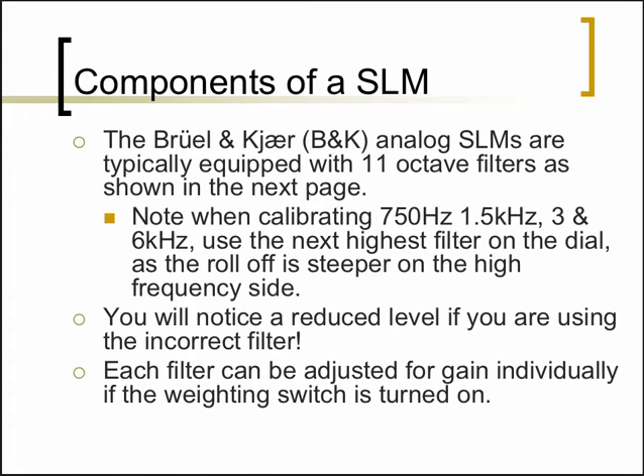So the B and K sound level meters, for instance, have 11 octave filters that are engaged depending upon the frequency that you're testing. Just a word of advice: if you're testing any inter-octave frequencies like 750 hertz, 1.5, 3, or 6 kilohertz, then one would use the next highest filter. So in that way, you're not underestimating the calibration value. Okay.